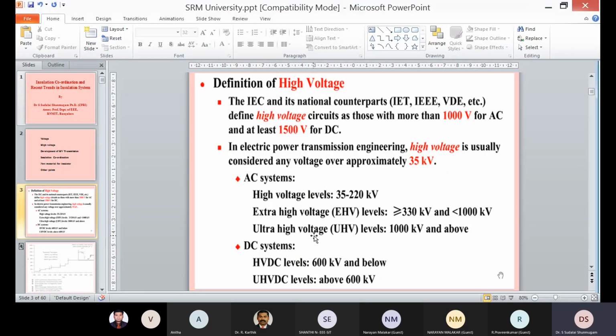If we go by the strict definition of standards, especially IEC and its national counterparts, the standard says that anything more than 1000 volt is high voltage in case of AC supply, and anything more than 1500 volt is high voltage in case of DC supply. Traditionally, by standard, this is the defining parameter. Anything more than 1000 volt for AC comes under the classification of high voltage. Anything more than 1500 volt traditionally comes under high voltage for DC power supply. That is the common nomenclature.